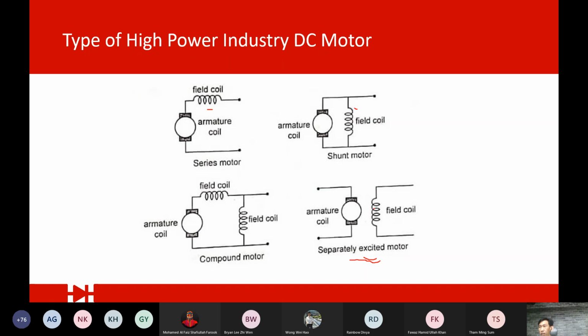The other one, for simplicity, is the series configuration. These two types are the most common in industry. With series, you just need one control rectifier, which applies to both the field and armature and controls them at the same time, so speed and torque are controlled together. But you cannot control individual torque and speed separately because they are connected in series. If you want more control, like a certain torque and a certain speed, then you need to use a separately excited motor.